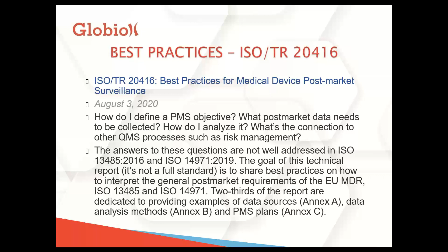All right, so we've identified sources of data. It's everywhere. Now what? As part of the PMS, you've got to consider the proper ways to analyze it. ISO technical report 20416, which we just talked about, offers this advice. It should be determined which parameters are analyzed and what the respective reference values are. For example, batches, sub-batches, total number of medical devices manufactured, hours and frequency of use, number of medical devices in use, patient populations. As an example, the downtime, which is a parameter of an electric medical device, can be compared with its hours of use, which would be the reference value.